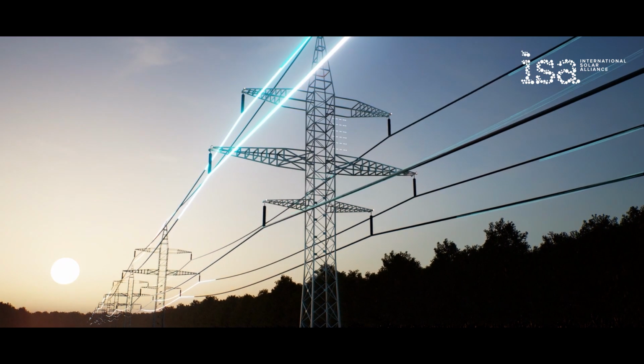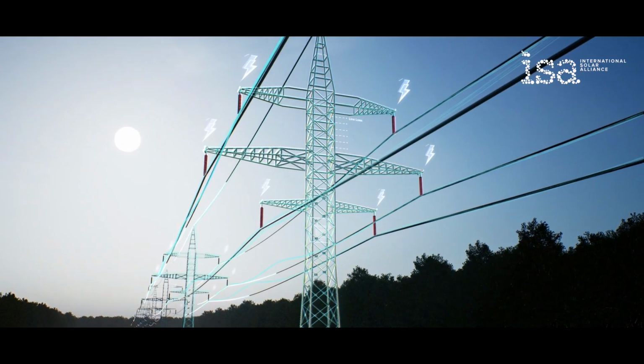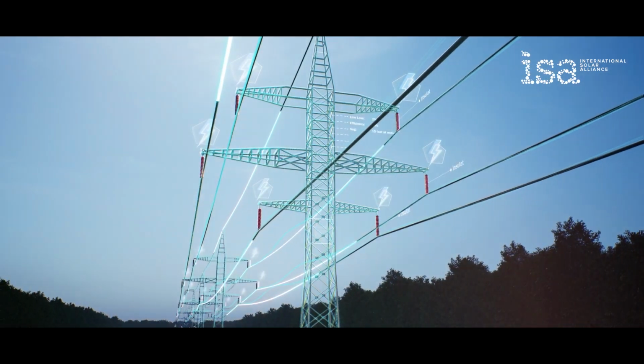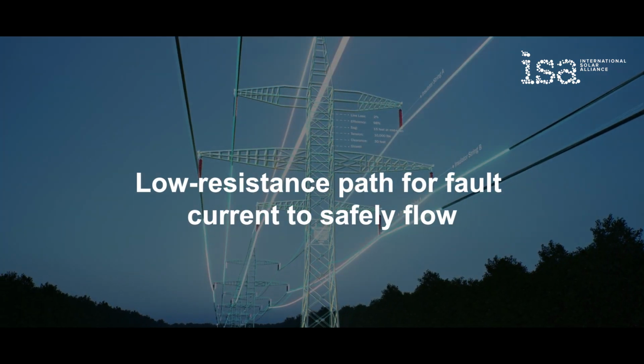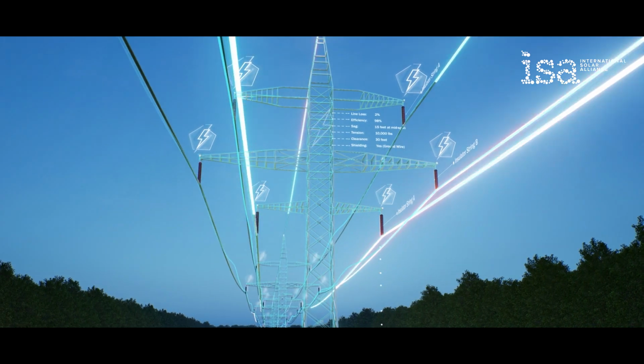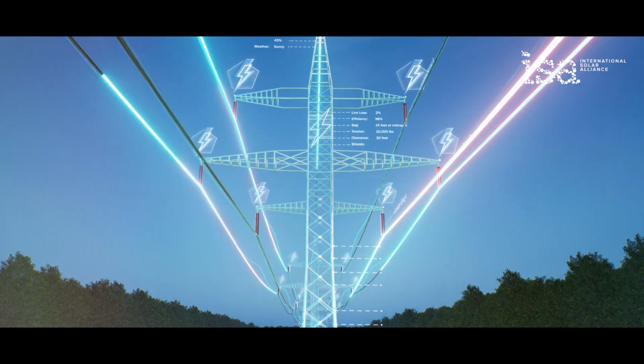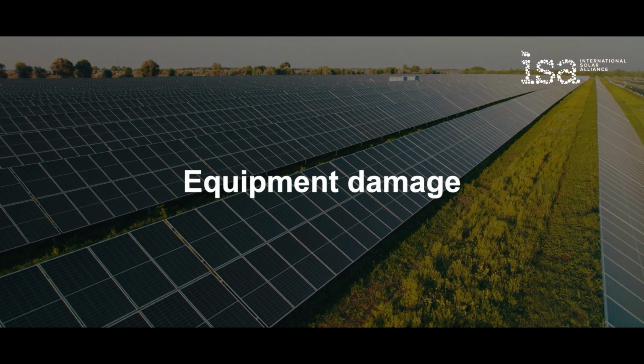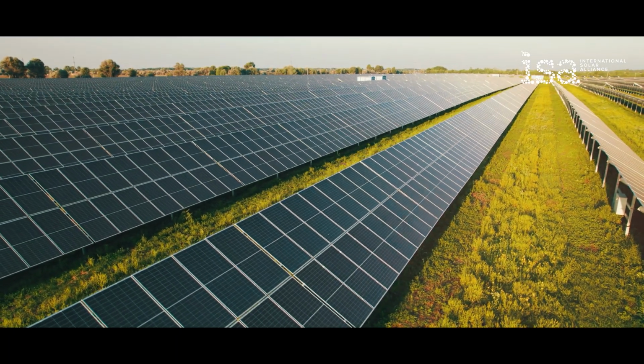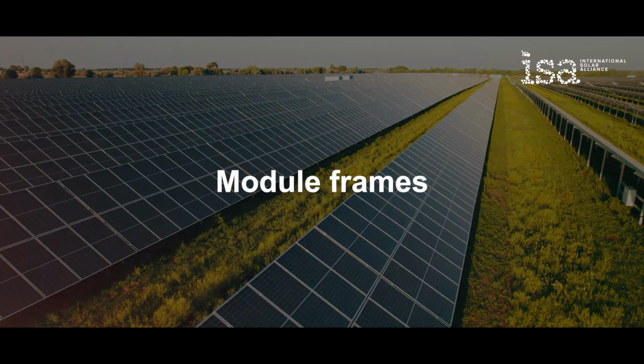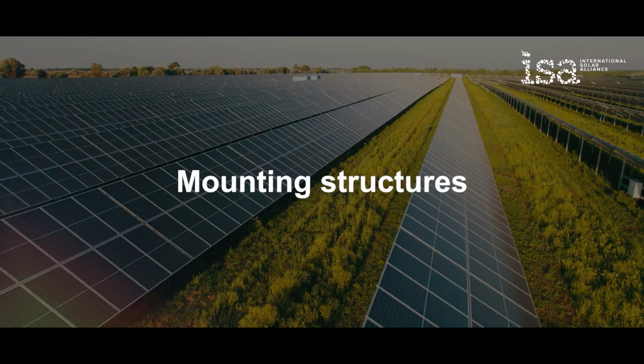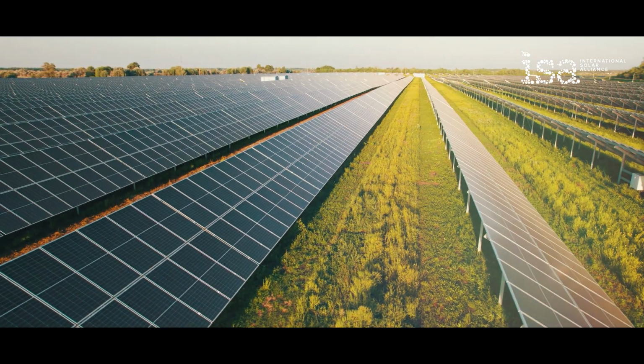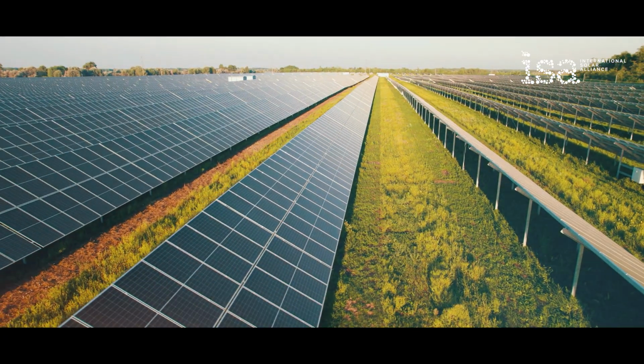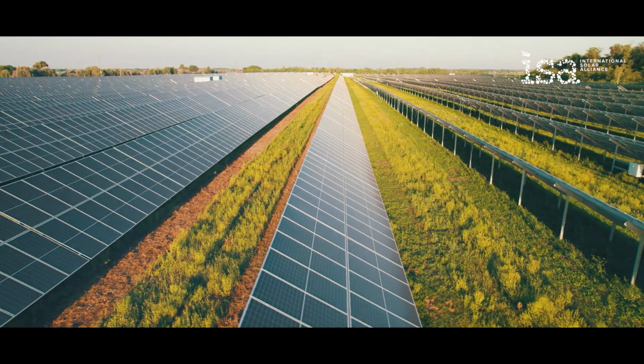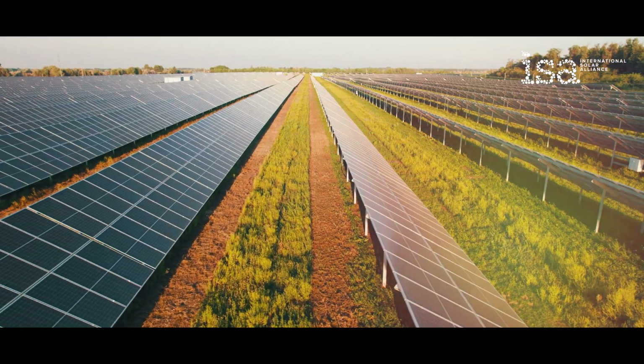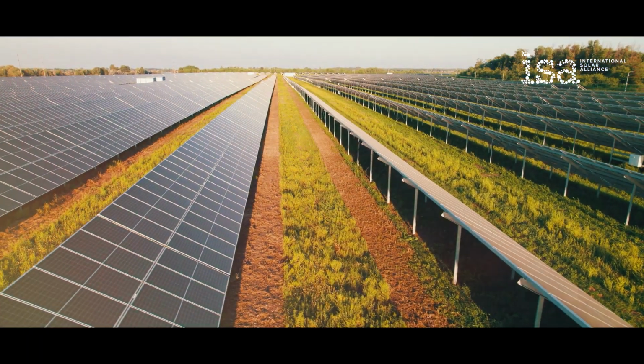Earthing is the backbone of electrical safety in any solar PV system. Its main function is to provide a low-resistance path for fault current to safely flow into the ground, as the name suggests. This helps prevent electric shocks, fire hazards, and equipment damage. All metallic non-current carrying parts, such as module frames, inverter enclosures, and mounting structures, must be connected to the earthing network. This ensures that if any fault current leaks due to insulation failure, it is safely discharged into the earth without harming the equipment or personnel.